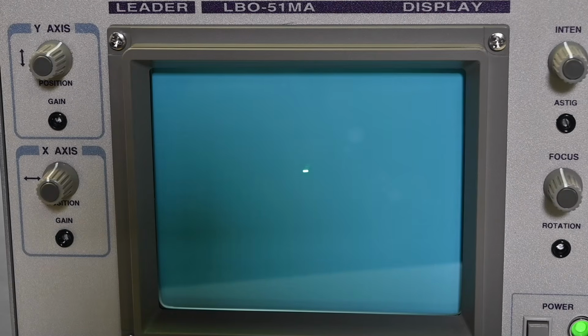There's fluorescent lighting and LED lighting around the bench, and all of that is electrically noisy. So now it's powered right off the AC line as it would normally be used, which means that the chassis is earth grounded, but it's still doing it. Then I thought, well, maybe because the top cover was removed, and the cover is metal and would add shielding, so I installed the top cover and it didn't change anything. It still had the same amount of deflection. So the cover is removed again, but it had no effect.